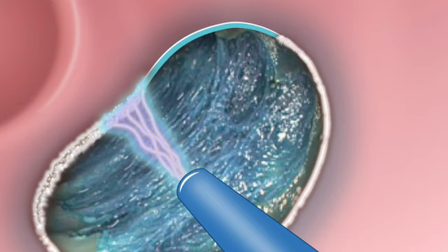Right, it's non-contact. Exactly. If the endoscopist pushes too close and actually touches the mucosa with the probe while firing, the physical pressure of the argon gas, which is flowing at nearly a liter per minute, gets forced directly into the submucosal plane. And the transcript mentions this causes a pneumatocyst. Yes. The gas literally dissects the tissue layers apart, creating this trapped pocket of argon within the gut wall. Oh, that sounds awful. It's a complication you desperately want to avoid. So that's distance. The second variable is power, or wattage. The higher the watts, the deeper the thermal burn.